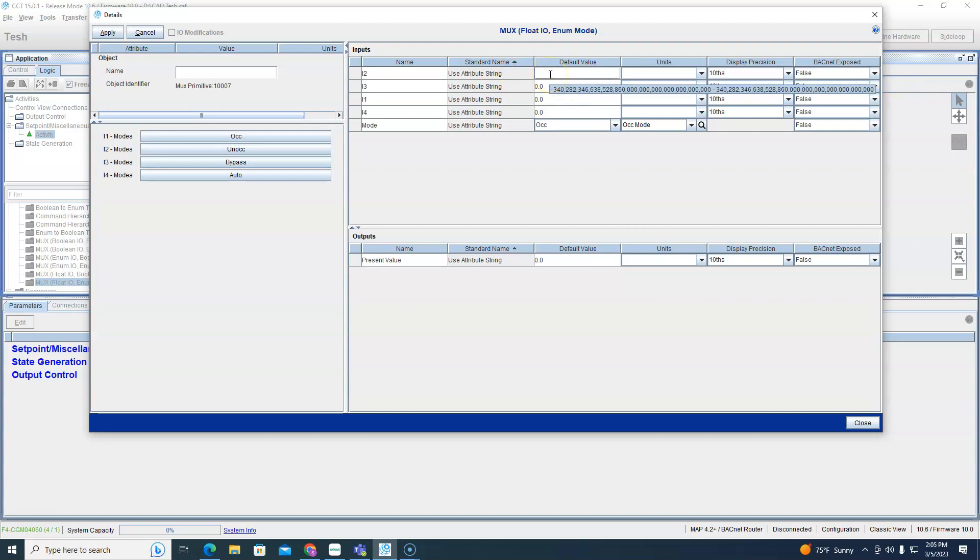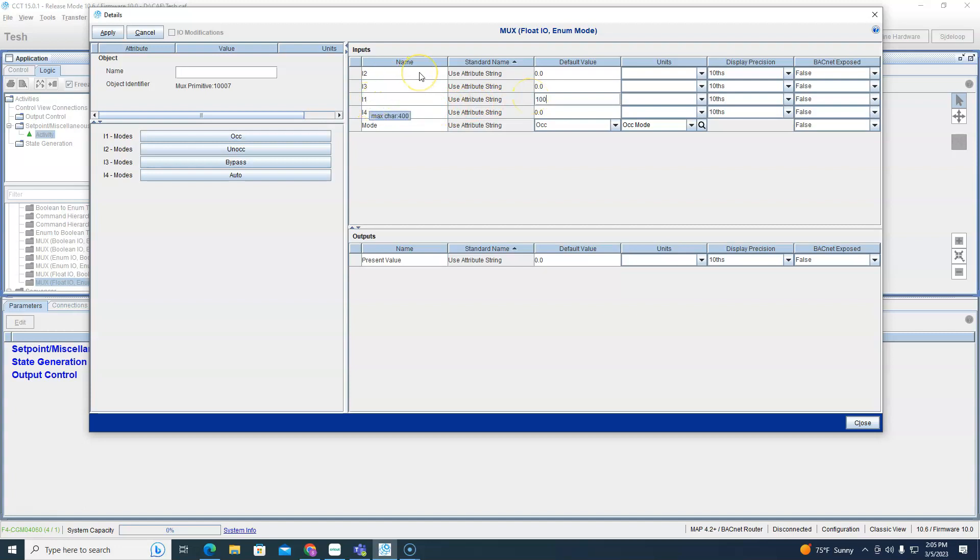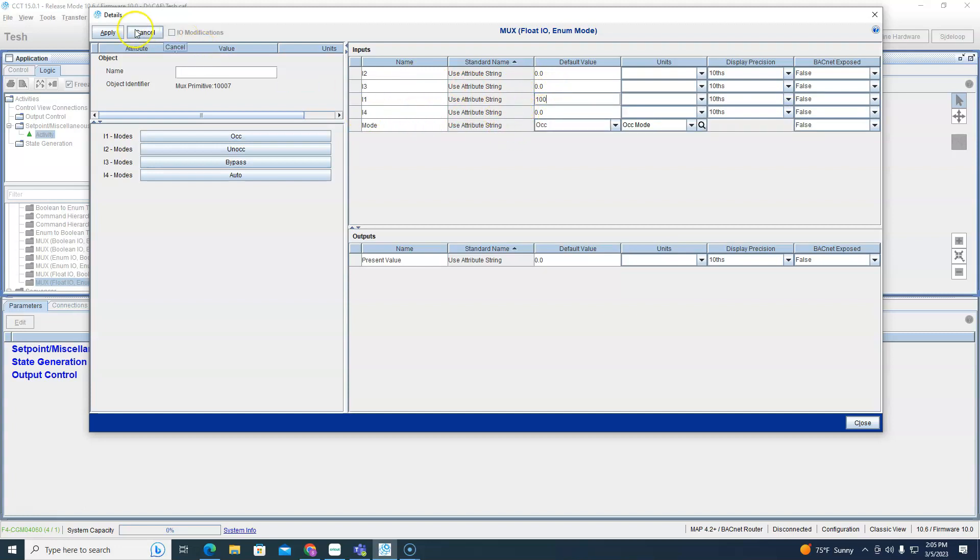So what can we do here? Well I mean we can modify this. Occupied we want it to go to 100 percent occupied. Okay perfect. Oh see I screwed up, that's not occupied that's unoccupied, one is down here. So you got to be careful, you got to watch where the numbers line up. Two is unoccupied, three is bypass, I'll leave that zero right now, and four is auto, we'll leave that.